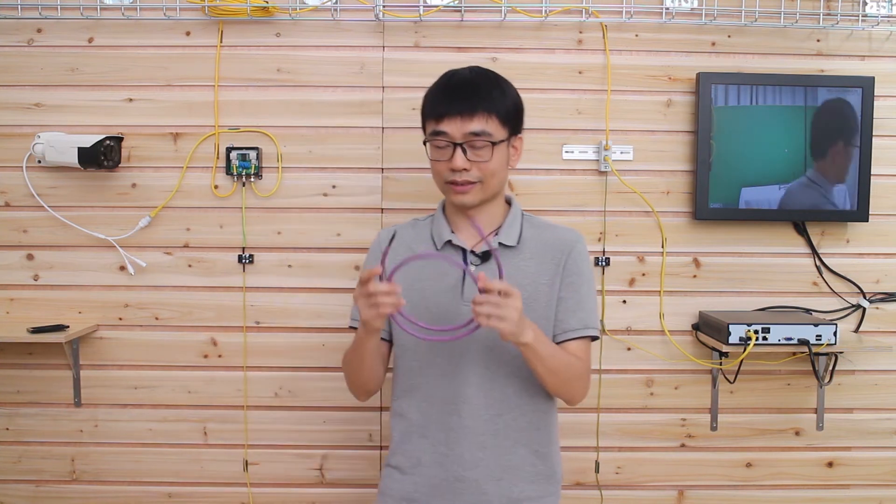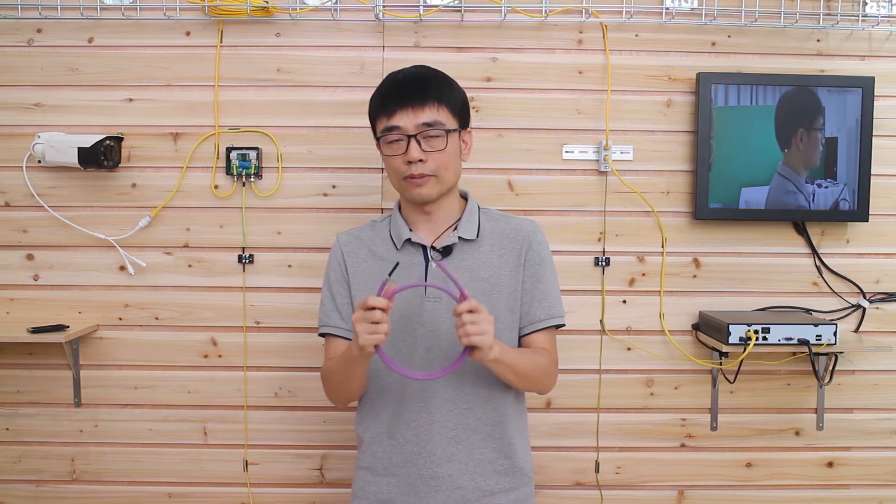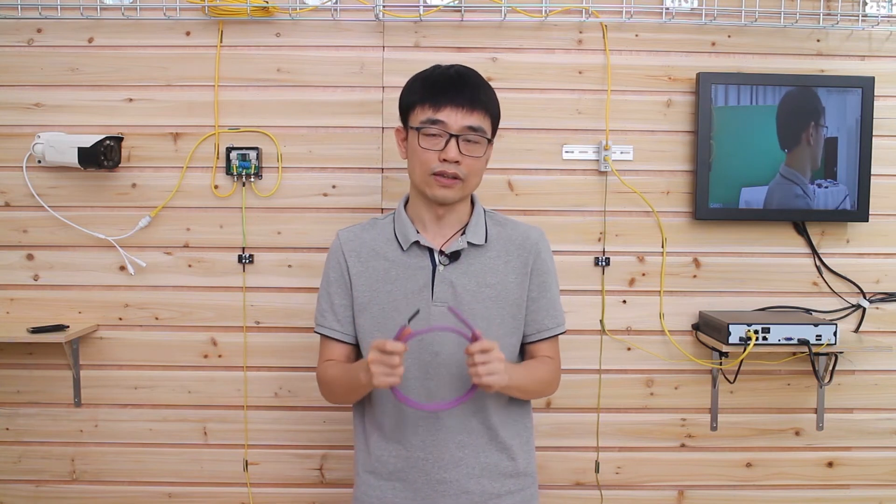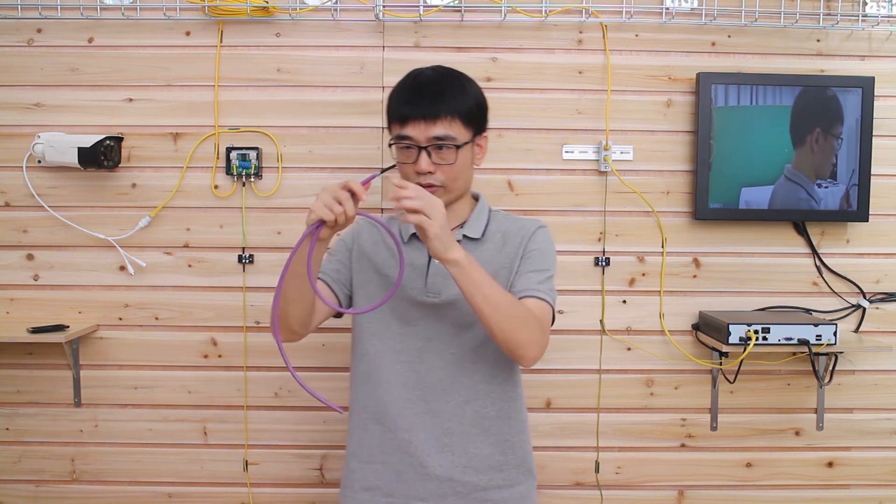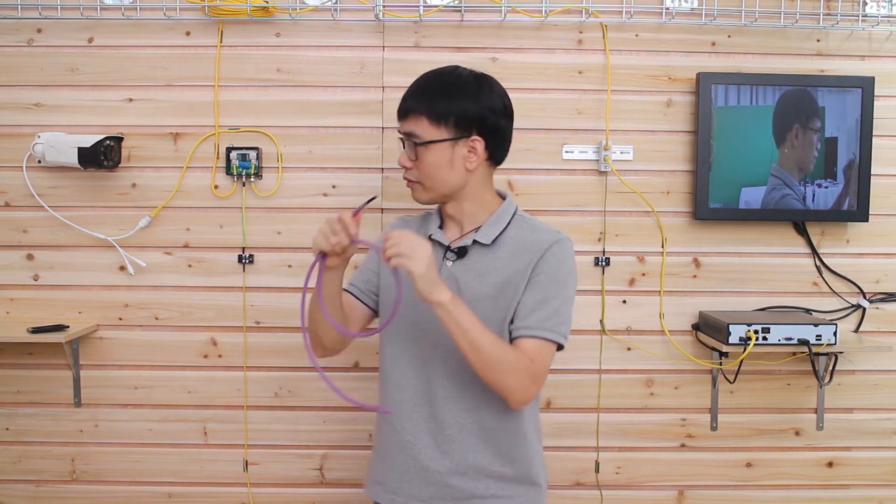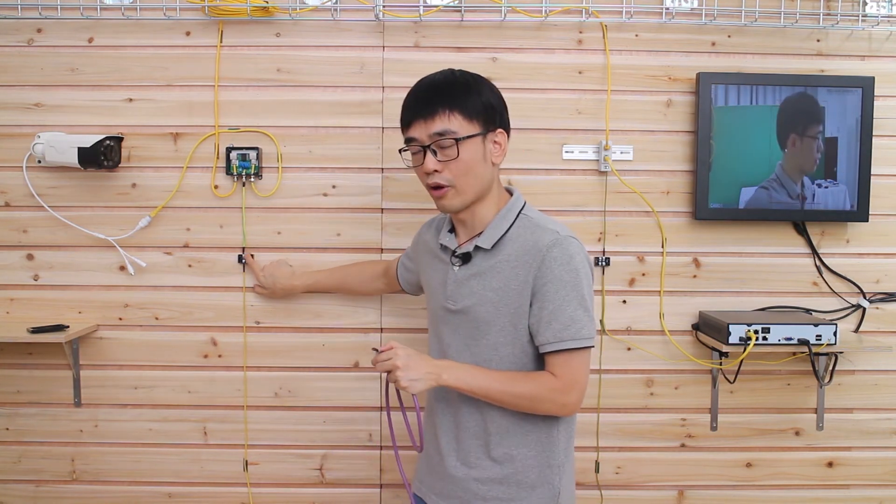There's still one thing people are thinking about: using shielded cable. That's a very good idea because shielded cable can enhance the surge protection. But only if you have grounded the shield independently to the grounding spot.